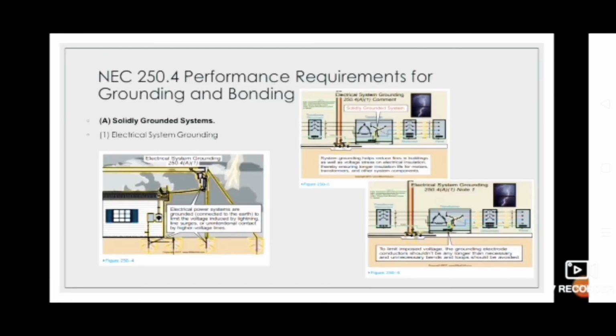Next, performance requirements for grounding and bonding, for grounding and also for ungrounding. For the grounding, we can see electrical system grounding. Electrical systems are grounded, connected to the earth, to limit the voltage induced by lightning, line surge, or unintentional contact by higher voltage lines.